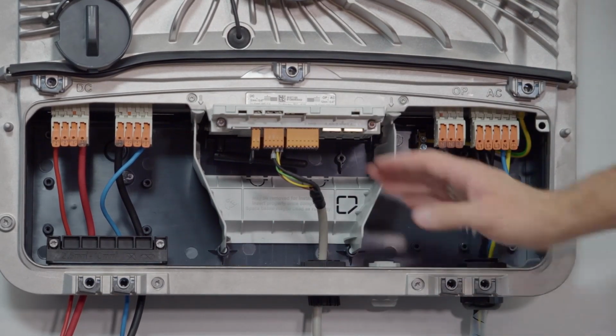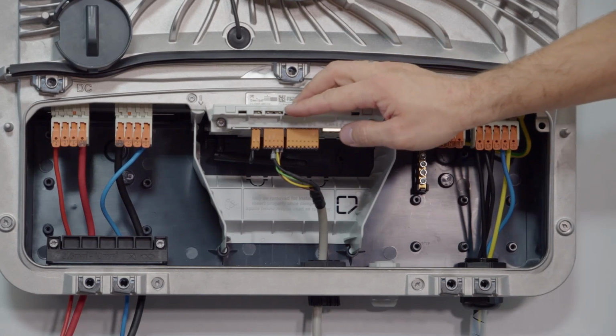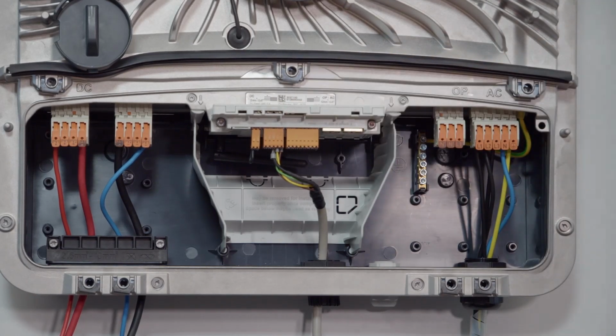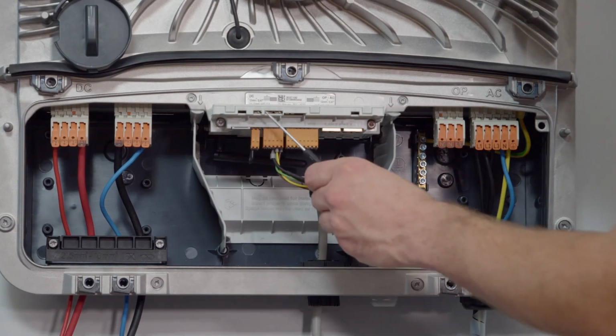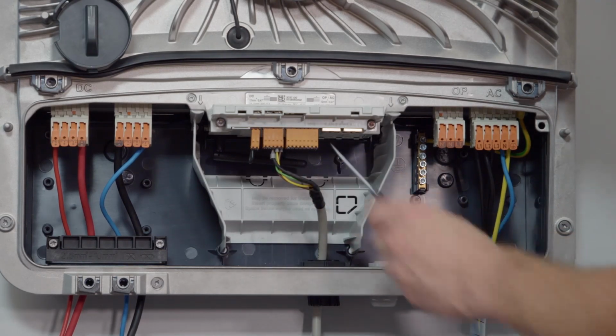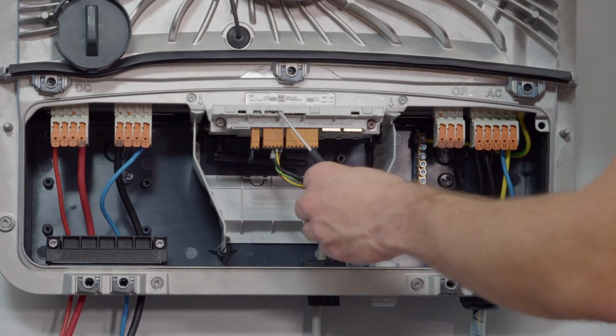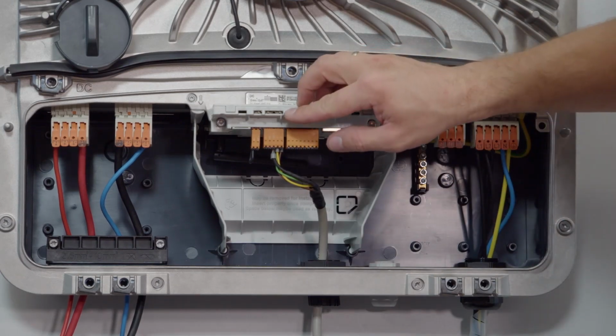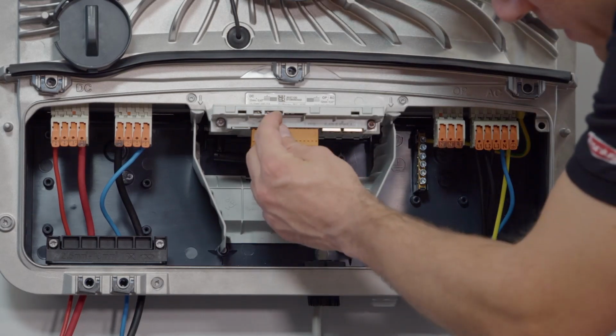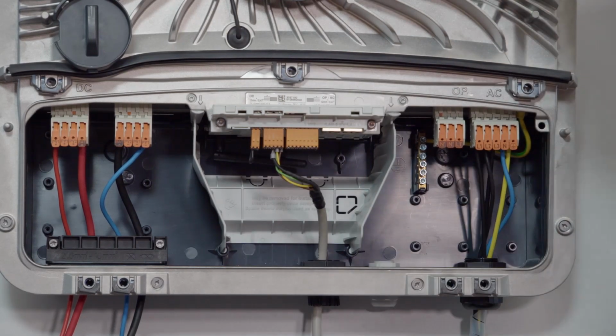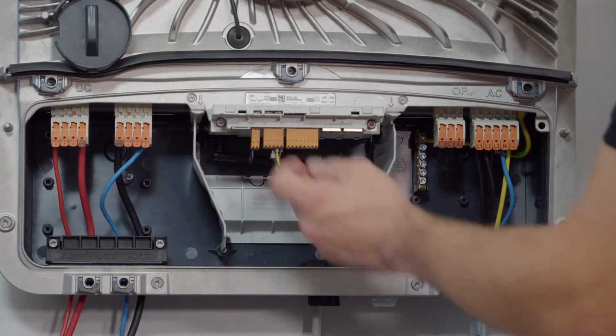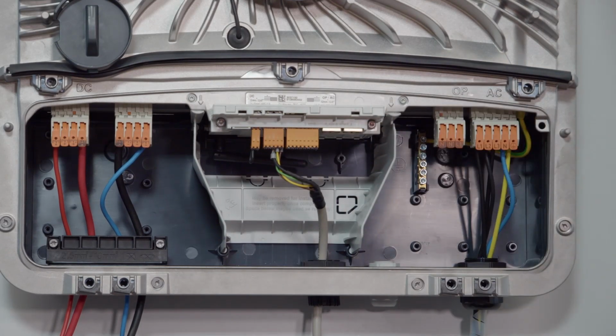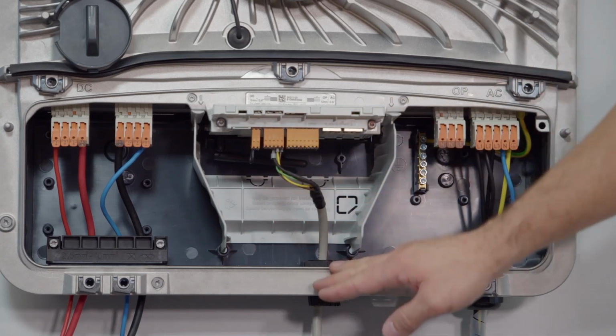Very important, for every Modbus communication line you need to do the termination resistance on the GEN24 Plus, and therefore you have 2 possibilities here. We have Modbus 0 and Modbus 1. In our case, we installed the Fronius smart meter to Modbus 1, and therefore we want to make sure that the termination resistance is switched to position 1, and therefore that means that the termination resistance is active and the 120 ohms resistance is active to terminate the line at the GEN24 Plus, which is our endpoint of the system.